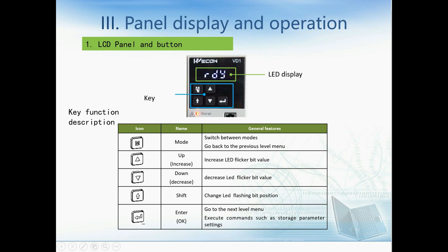This is the LCD panel and buttons. Just like most servo drives in the market, there is an LED display and five buttons. The first button is the M switch, used for switching between modes or going back to the previous level menu. The up button increases the LED flashing bit value, and the down button decreases it. Another button changes the LED flashing bit position. The last one is the Enter button for going to the next level menu or executing commands such as storing parameter settings.